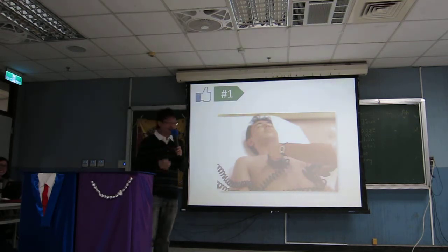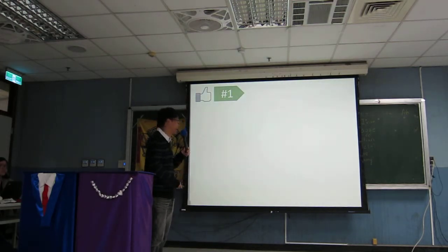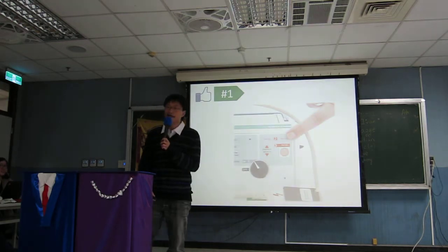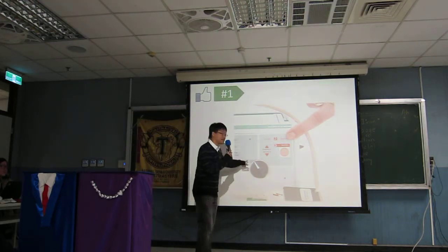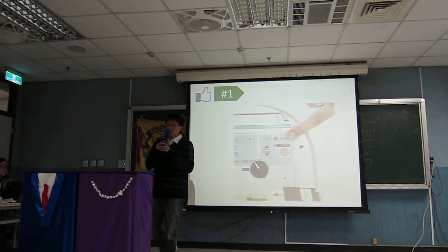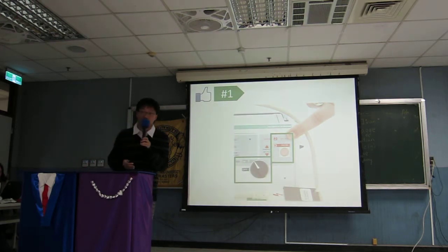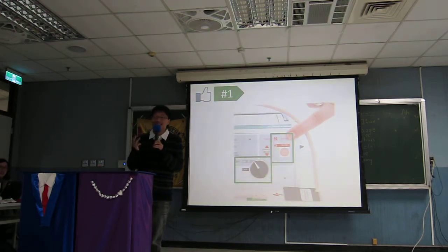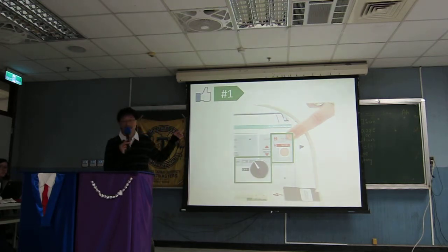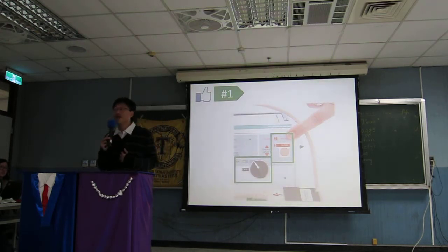Yes, just like this. Now, if today I'm an exhausted doctor, and I come to the front of the defibrillator, wow, it's a little bit complicated, right? And I'm so tired. But I can simply follow the SOP. As you can see, there are numbers beside the buttons that need to be pressed. First, I switch on the power. Second, I press the analyze button to see if the patient is suitable for defibrillation. And third, I press the shock button. It's as simple as this. 3 easy steps. With this user-friendly interface, I can avoid errors like forgetting to switch on the power, even if I'm really tired.